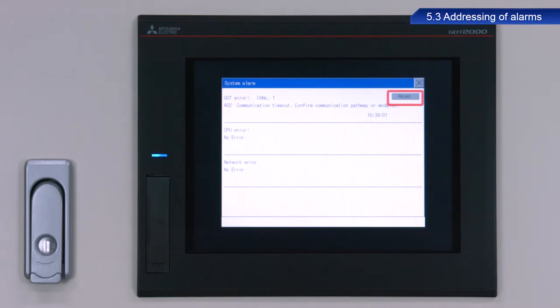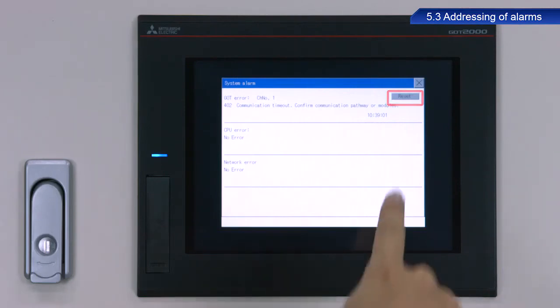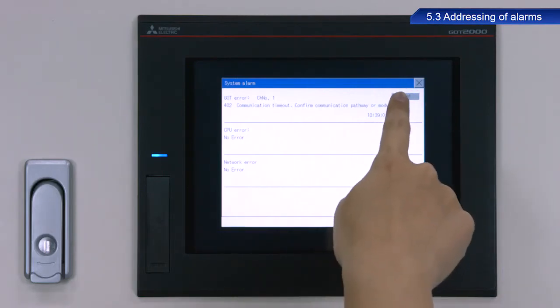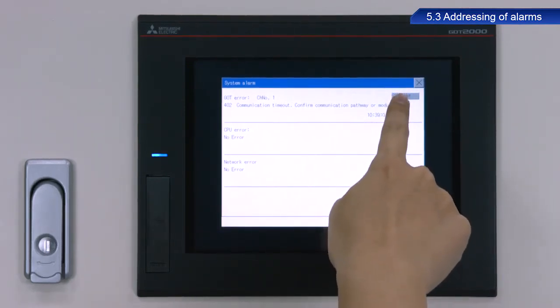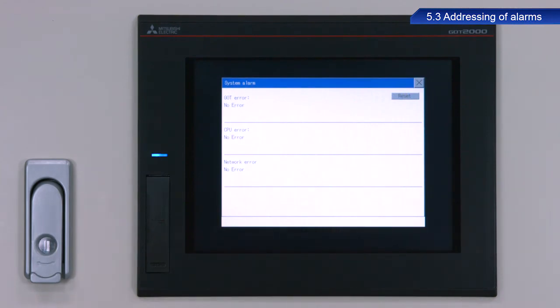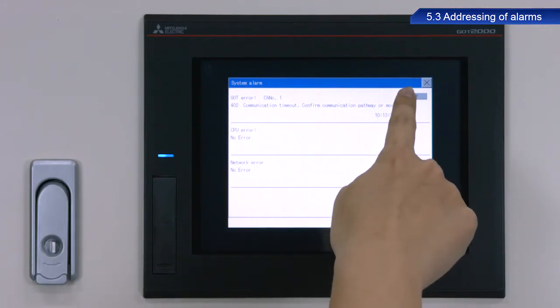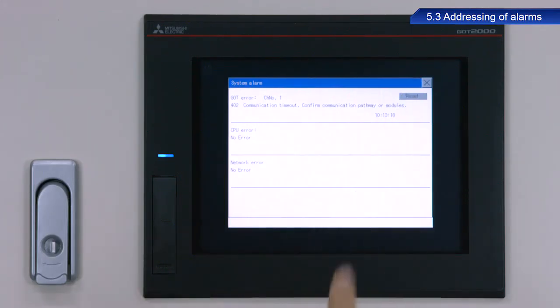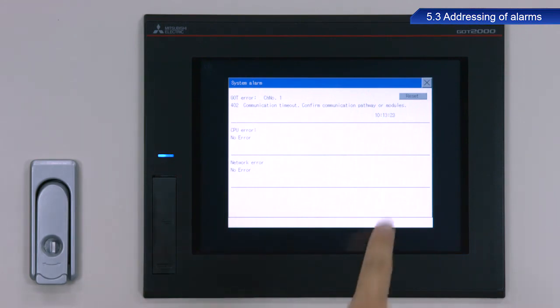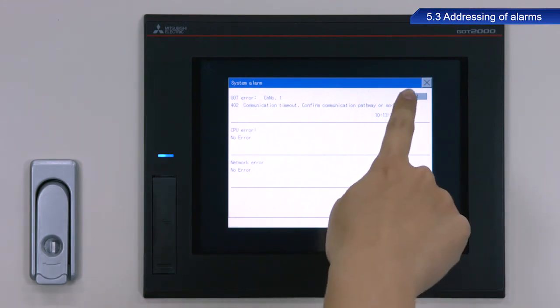Press the reset button on the system alarm screen to reset the system alarm. A note of caution here: if the cause of the system alarm is not resolved, pressing the reset button will not clear the alarm from the GOT system alarm display.